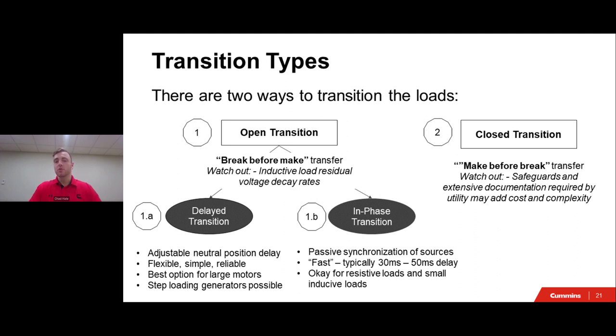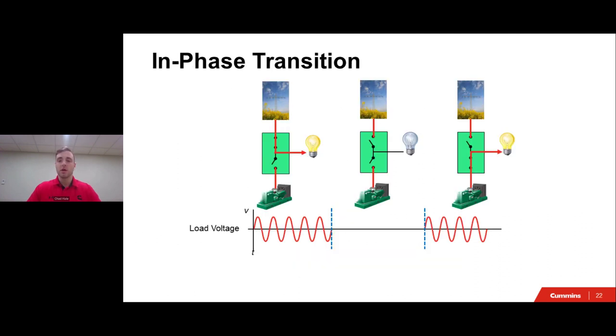So now that we've covered both the open and closed, let's dive a little bit deeper into those delay transition and in-phase transitions, and then lastly, closed. So in-phase transition. In this graphic here, you can see that there are two live sources. On the top, you have your utility. On the bottom, you have your gen. On the far left of the diagram, imagine that the automatic transfer switch starts to sense that there is something wrong with the normal source of power, so it wants to switch over to that emergency power source, being that generator in the graphic, which is what we can see happening in the middle of this graphic. The automatic transfer switch has opened to the utility, which means that it has come off, which causes a brief interruption of power to your loads. And then, as you can see in the diagram, the load voltage has completely gone away.